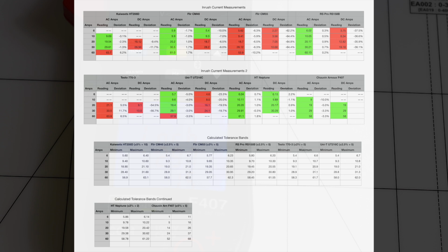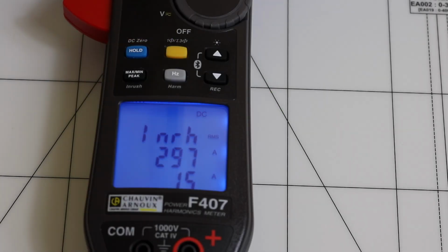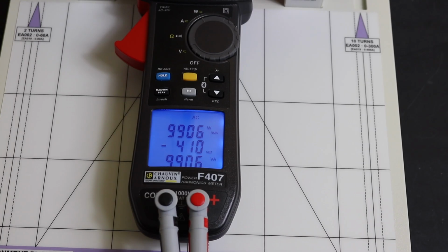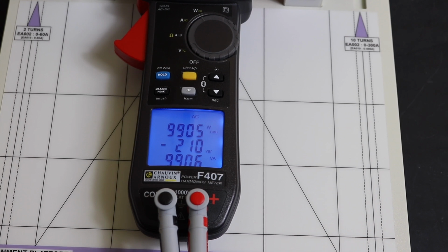But this is the rest of the results compared to the other instruments that I've tested in the past, and you can see AC and DC, it's reading perfectly well, obviously aimed more at the higher currents than what I've been previously testing, but yeah, it's an interesting function that Chauvin Arnoux have put onto the instrument there. Not usually see trigger levels and DC inrush measurement on a clamp meter before. So we'll just finish this off with a little quick demo of the power functionality here.